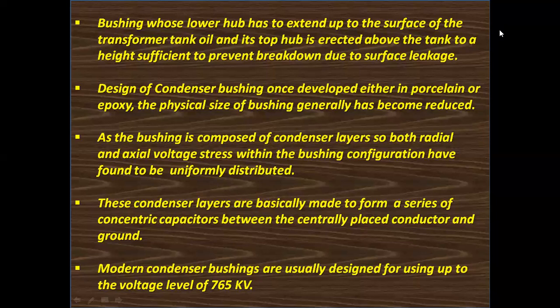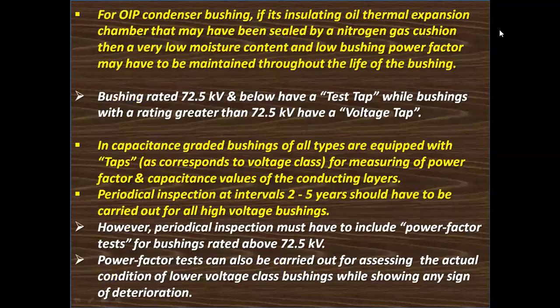Modern condenser bushings are usually designed for use up to the voltage level of 765 kV. For OIP condenser bushing, if its insulating oil thermal expansion chamber has been sealed by a nitrogen gas cushion, then a very low moisture content and low bushing power factor have to be maintained throughout the life of the bushing.